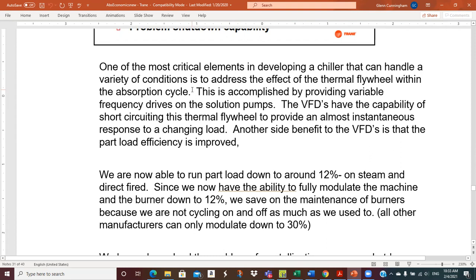So once you put it in, especially in the old days, you were still going to get the refrigeration out, whether you needed it or not. If conditions had changed, you might be producing refrigeration that you don't need just because the machine doesn't respond very quickly. So some of the things that they've done to give better response times is providing variable frequency drives on solution pumps. VFDs have the capability of short-circuiting this thermal flywheel to provide almost instantaneous response to changing load. And of course, the other benefit is it reduces the pump part load energy. So the efficiency is improved.